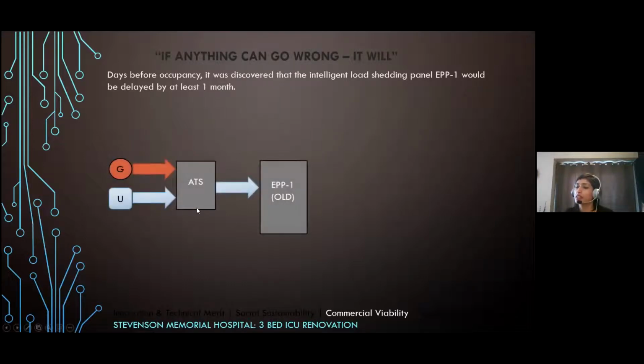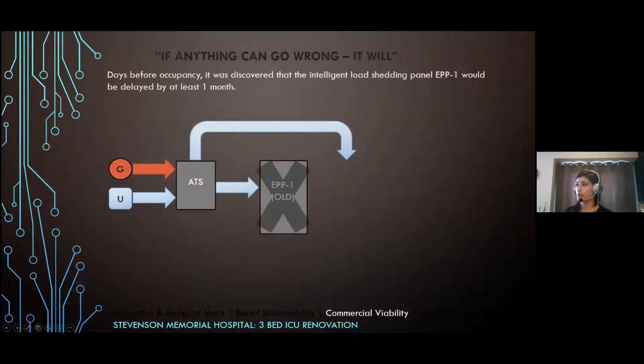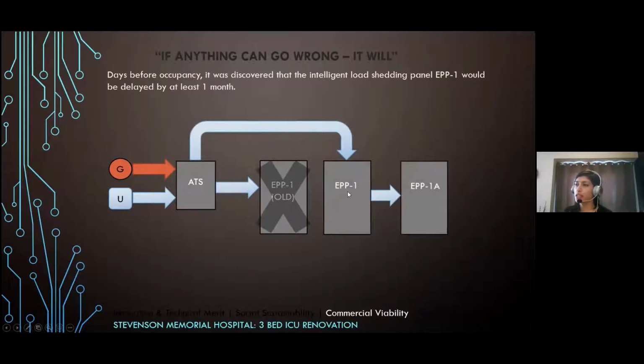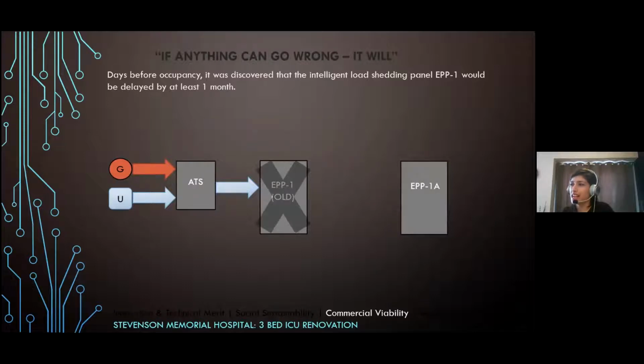So here's our single line. I'll explain to you what we were dealing with. Our plan was to replace EPP1 with a new panel. So we were going to remove the existing panel board and bring in a new panel board. It, in reality, consisted of two panels, one sub-fed from the existing. So panel 1A here was actually sub-fed from the existing EPP1. Now we were told that the main panel wasn't going to arrive for a month. However, that sub-panel EPP1A had been delivered and it was on site. And we didn't want to wait a month to get that first panel to be able to open our ICU.